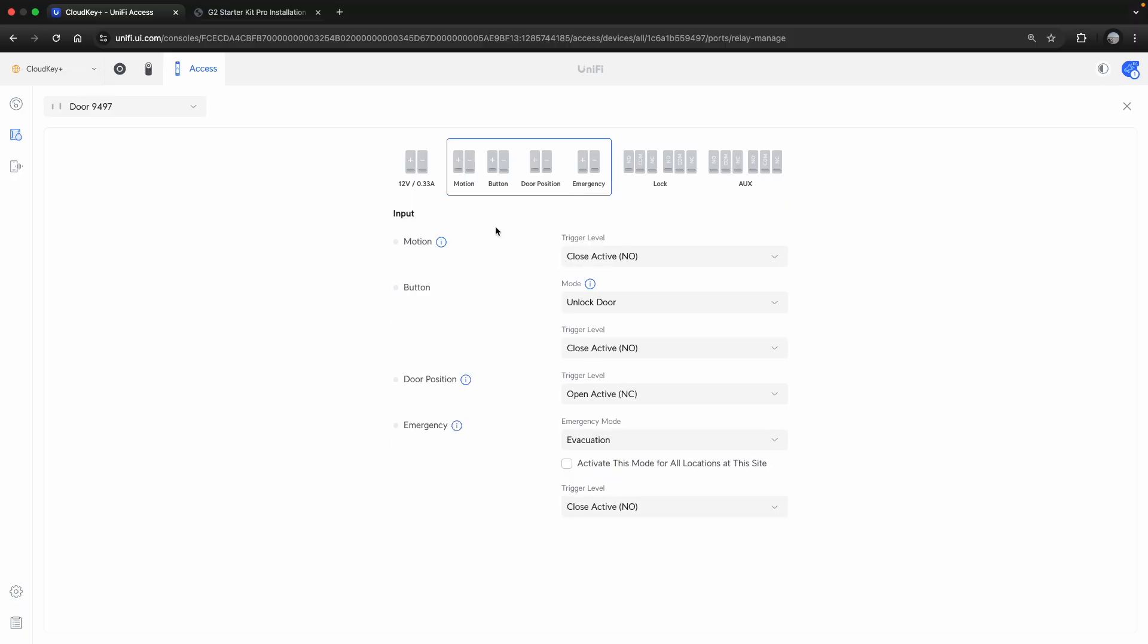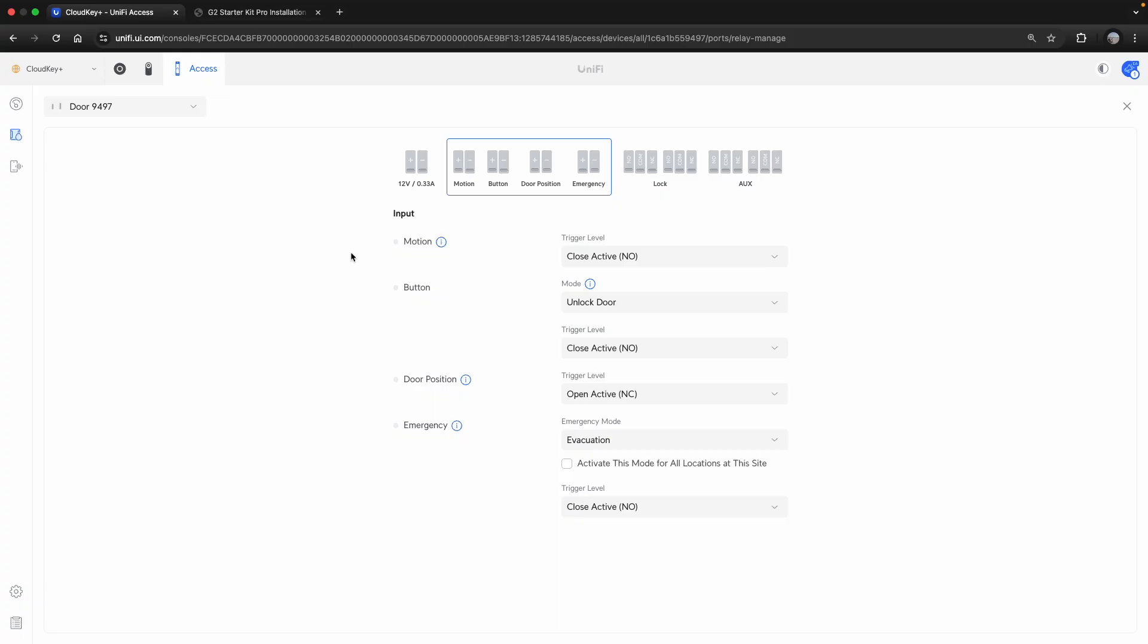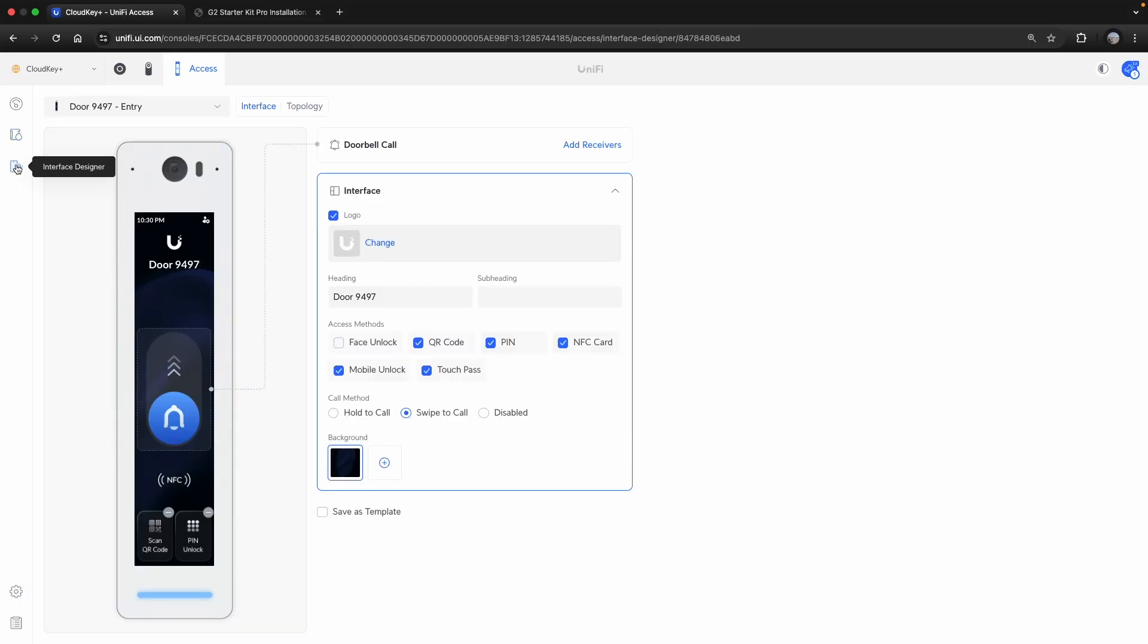I can also do stuff like triggering the door to unlock based on motion. I can do push buttons. I can set the state of those push buttons, normally open, closed. And I can say what happens in case of emergency with keyed emergency override or something similar. So again, very intuitive to do and work through this to what is actually present in your environment.